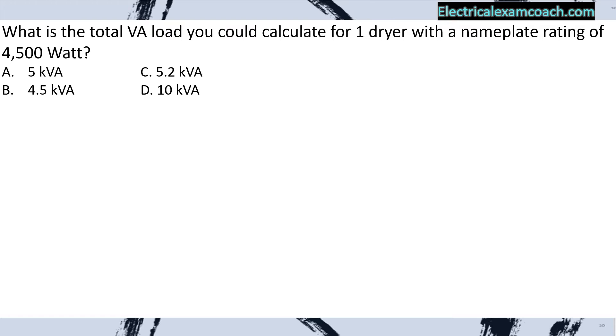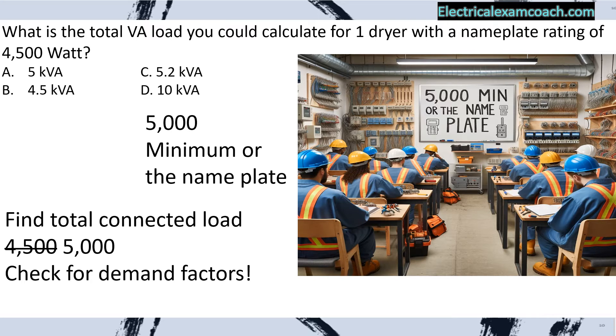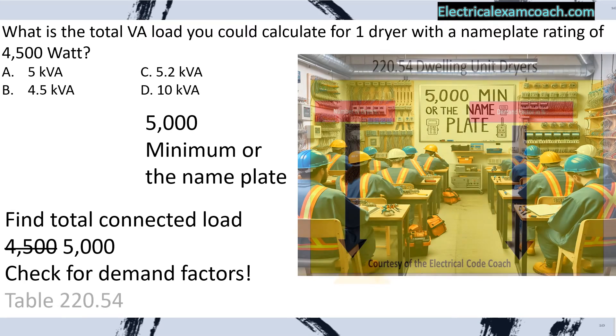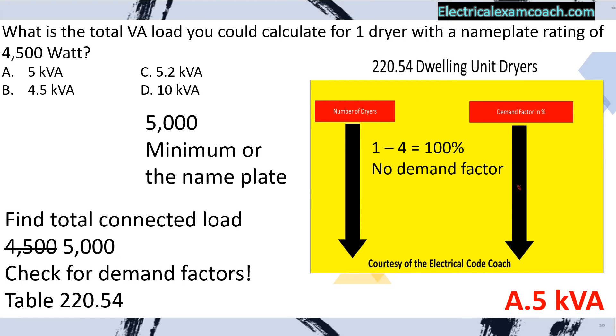What is the total VA load you would calculate for one dryer with a nameplate rating of 4,500 watts? First, we find the total connected load. We know that we have to use a 5,000 VA minimum or the nameplate, whichever is greater — so the 4,500 is out and the 5,000 remains. We then check for demand factors in table 220.54, and find that one through four dryers is at 100%, meaning there is no demand factor. Answer: A.